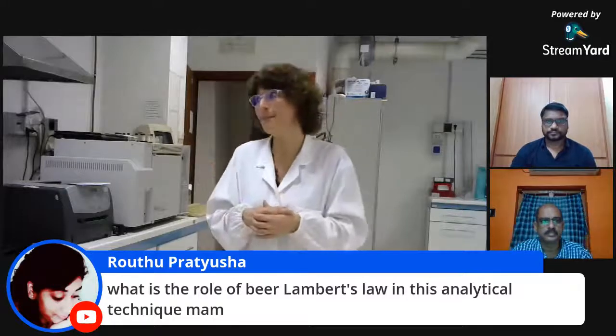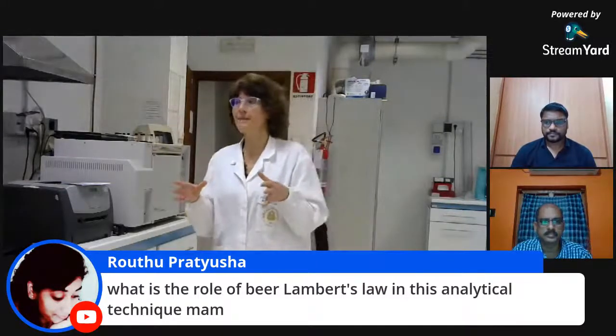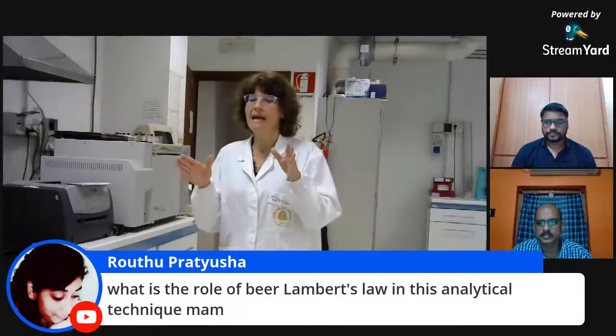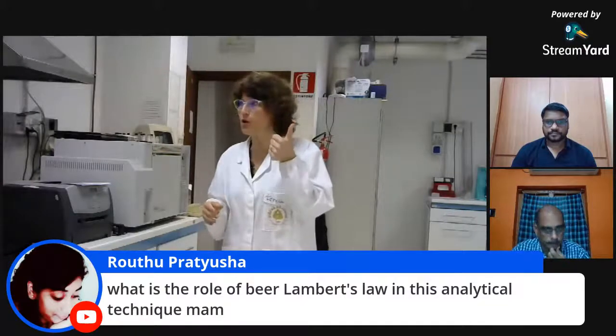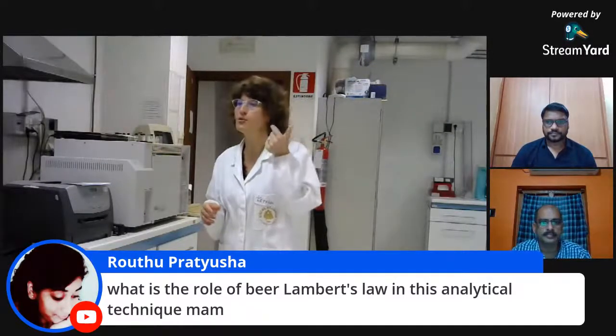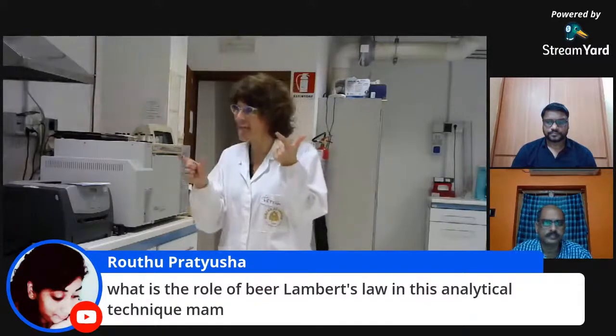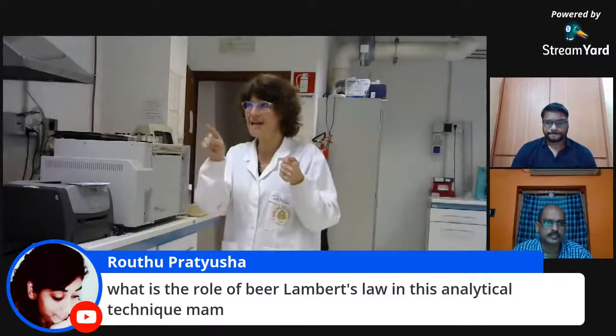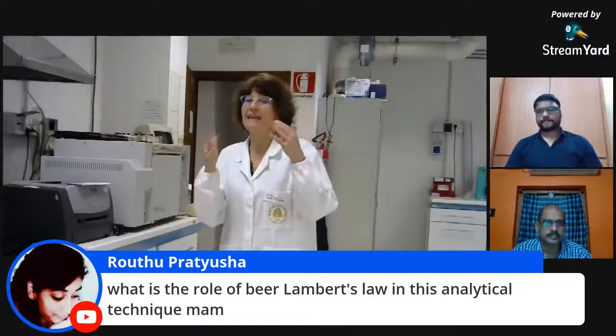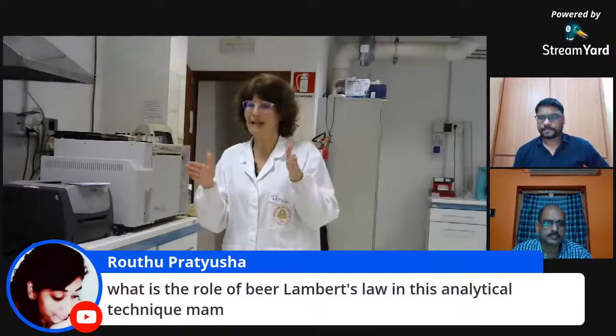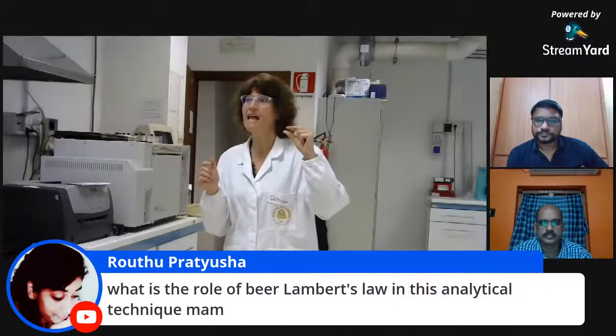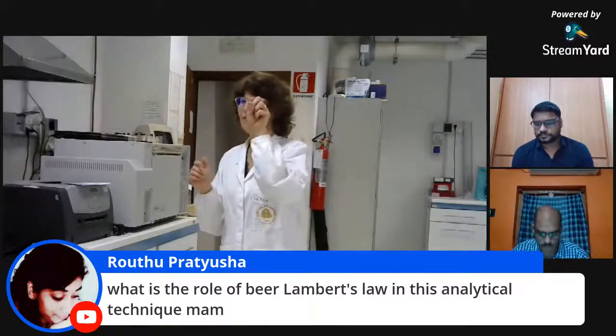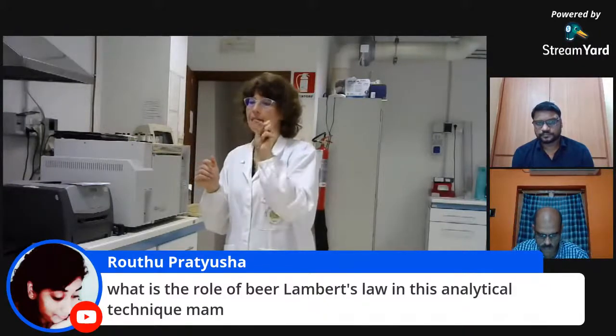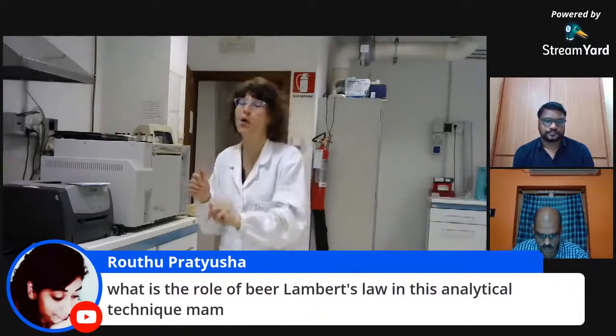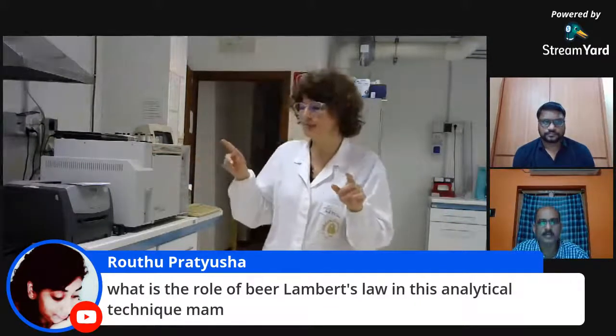Anyhow, which is the role of the Lambert-Beer law in this analytical technique? Well, the Lambert-Beer law is important because the absorbance is related not only to the concentration of the analyte, but also to the optical path of the cell. And as I told you before, the Z geometry results in an acceptably long optical path with a minimum cell volume. So the geometry of the detector is actually due to the Lambert-Beer law. So it is crucial. But in the Lambert-Beer law, there's also another parameter.